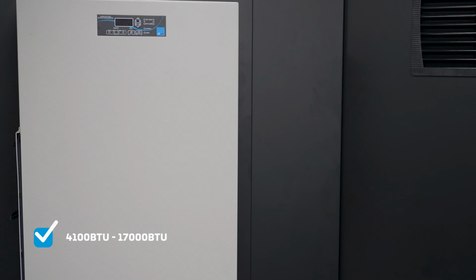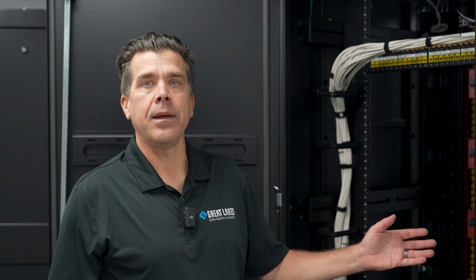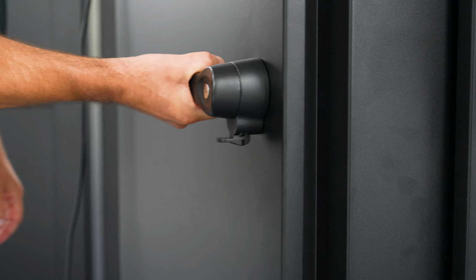A standard feature on the NEMA-12 cabinet is a defeater handle. This handle is keyed for security, but it can also accept a padlock for additional security. Standard on the NEMA-12 cabinet on the front and rear doors is a plunger switch utilized to turn off the AC when the door is open. You would want the AC to turn off so you can eliminate any chance of condensation in the cabinet while the door is open. Another thing that you will need is a completely sealed cabinet.